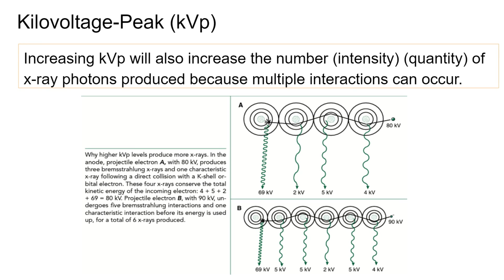As a matter of fact, you have to be careful when you go down in kV, because there's a rule. You have to have a minimum amount of kV to penetrate the part, even though 98% of it gets stuck in you. So I guess we're talking about the 2% that actually makes it through as penetrating. But if you don't even have that, then you have nothing. There's only so low you can go at a low kV because you risk not penetrating the part. So you have to have at least enough to penetrate the part.